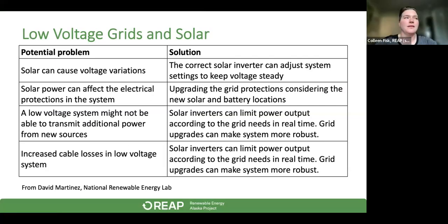So McGrath has a low voltage grid. With a low voltage system, you tend to have increased cable losses, and any changes to that voltage can have a bigger impact on the frequency of the grid. Because the frequency needs to stay within that narrow range, as close to 60 hertz as possible, adding in things like renewables like solar can have a harder impact on that frequency.